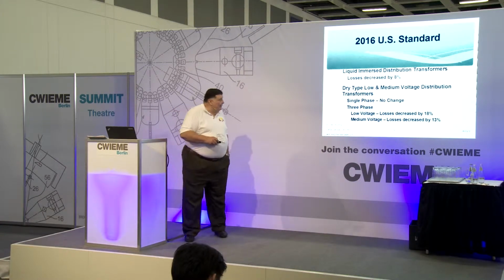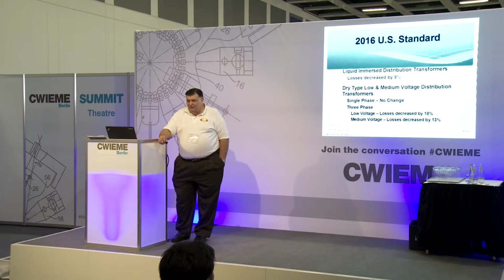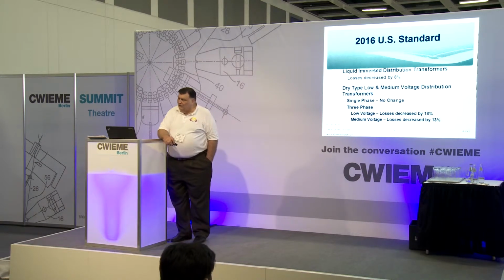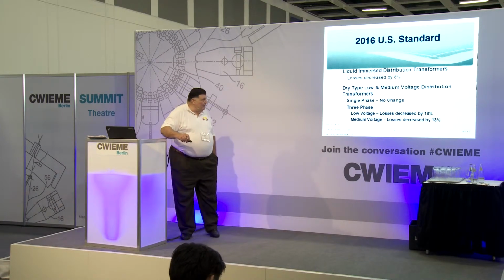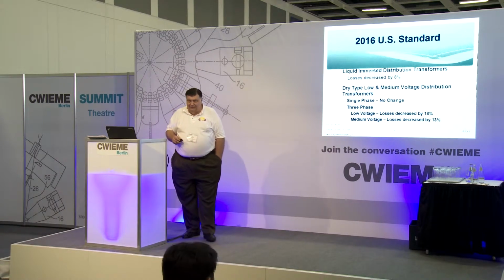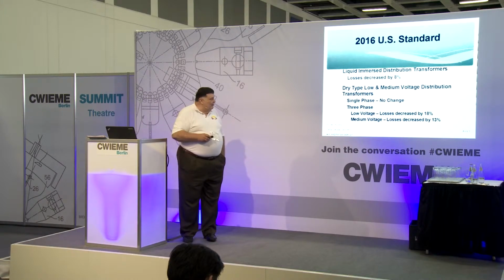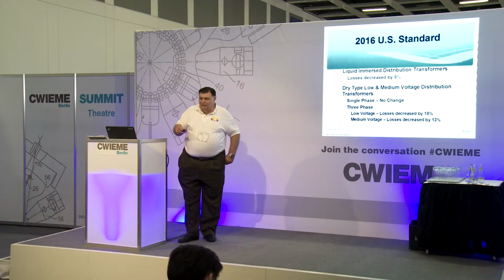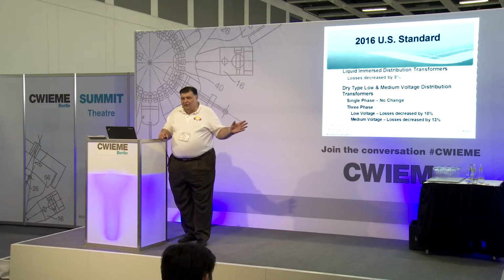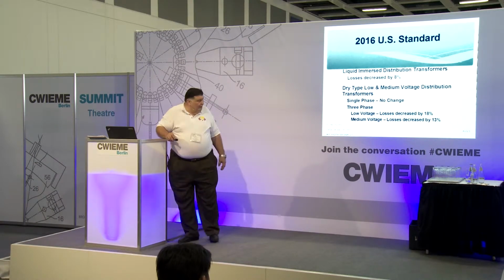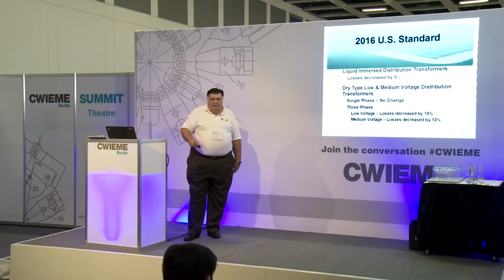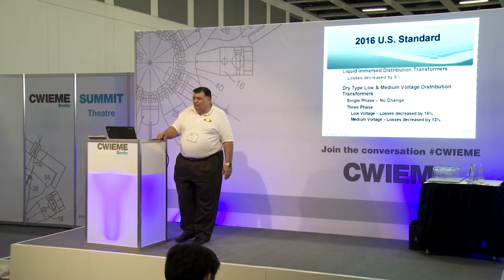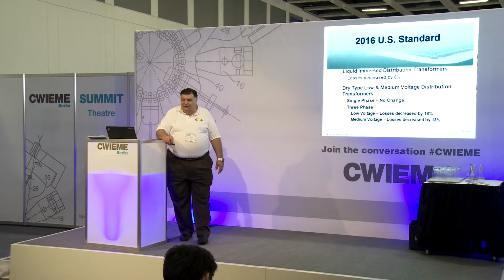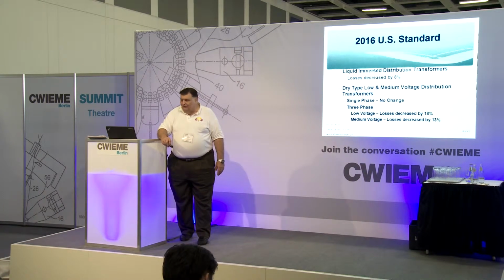The US standard: liquid immersed transformers have to decrease losses by another 8%. That will make the typical US distribution liquid immersed transformer about 99.3% efficient. In the previous standard in the US, dry type transformers were not even talked about. In the new standard, for medium and low voltage dry type, single phase transformers have no change, and that's the smallest part of the dry type business. Three-phase low voltage transformers have to decrease losses by 18%, and medium voltage by 13%. Those are major changes in the dry type transformers.